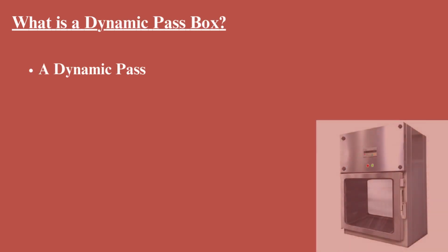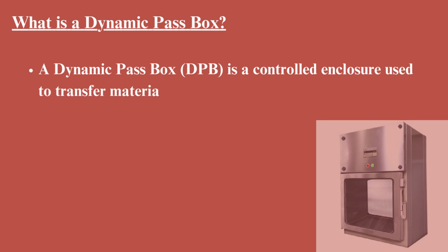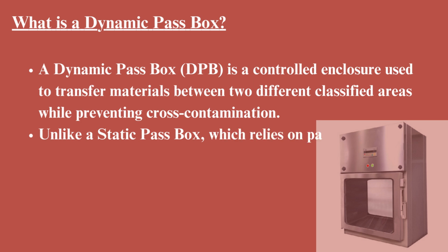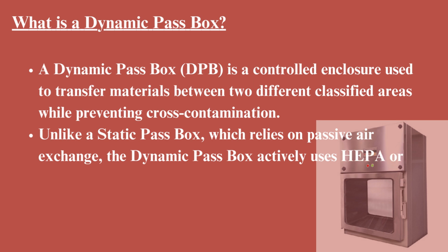What is a dynamic passbox? A dynamic passbox is a controlled enclosure used to transfer materials between two different classified areas while preventing cross-contamination.